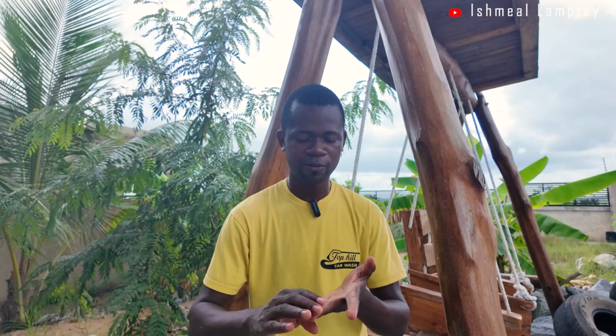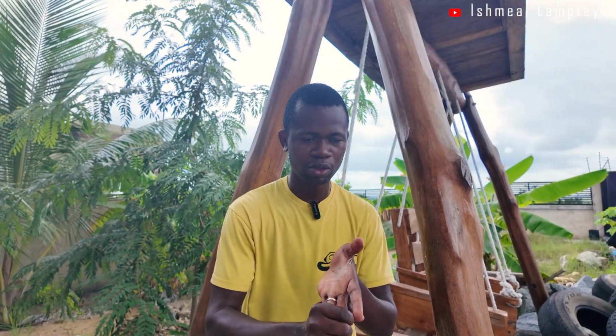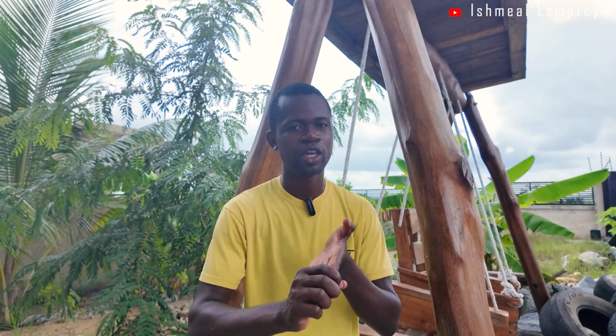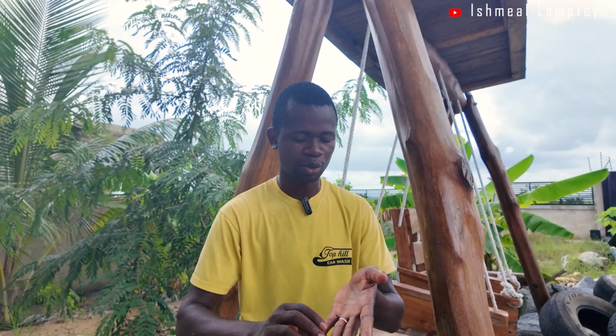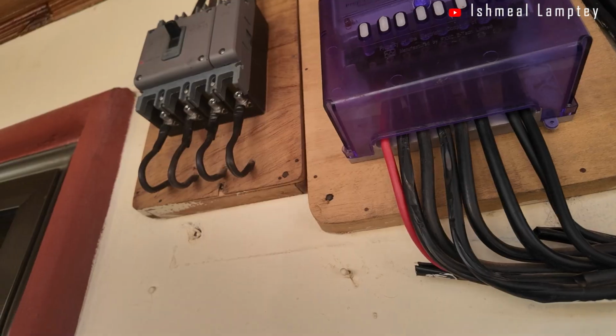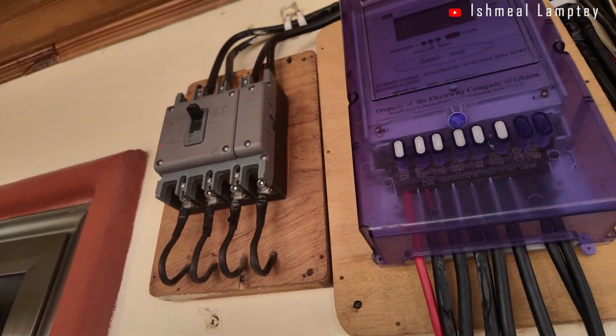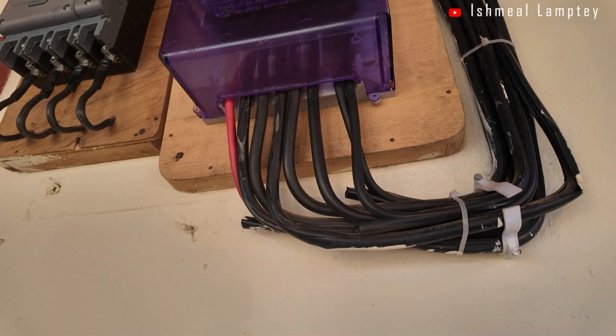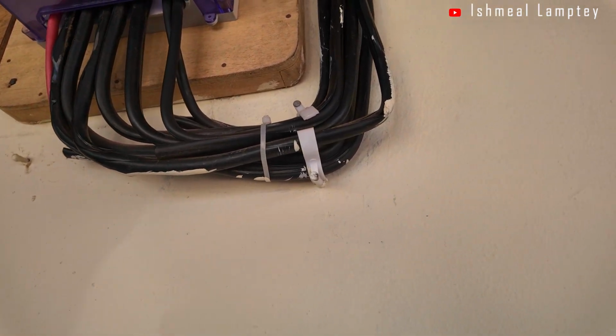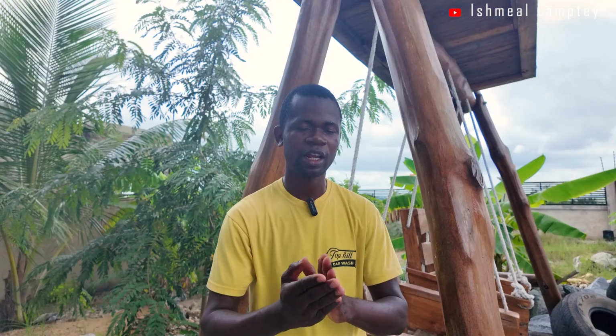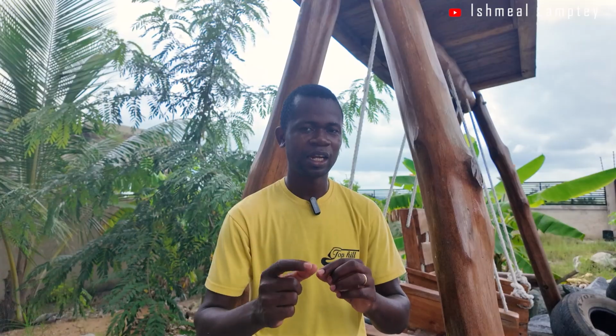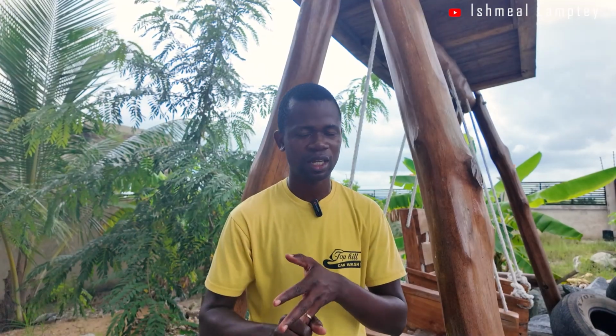So with the cables, you have 3 sets of cables. If you have the 3-phase option, it means you have 4 cables coming from the grid to your house. So you have line 1, line 2, line 3, and then you have neutral as part of it. The configuration of the inverter is the same thing. The AC input requires that, and then the AC output is also basically that. So we have 4 sets of cables coming in, another 4 sets of cables, making a total of 8 cables. Then in addition to that, we have 2 more cables, one coming in and one going out. So 8 plus 2 gives you a total of 10 pieces of cables.